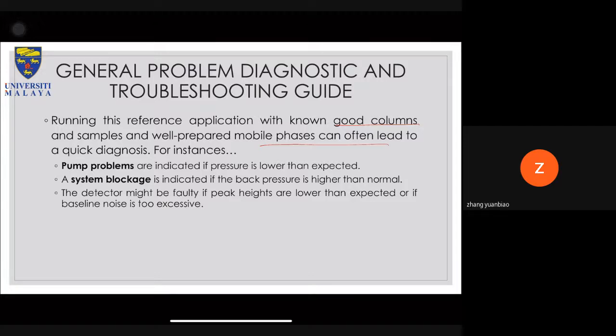Additionally, if a system blockage is indicated because the back pressure is too high compared to normal, then you want to go back and see your records in terms of what samples you have run previously. The sample you ran previously might contain a little bit of C18 lipid, in a very small quantity, so that it does not straight away block your column, but as you gradually increase the number of injections and analyses, lipids build up inside your column and finally result in a high back pressure. Okay, so record keeping is very important, especially for troubleshooting.